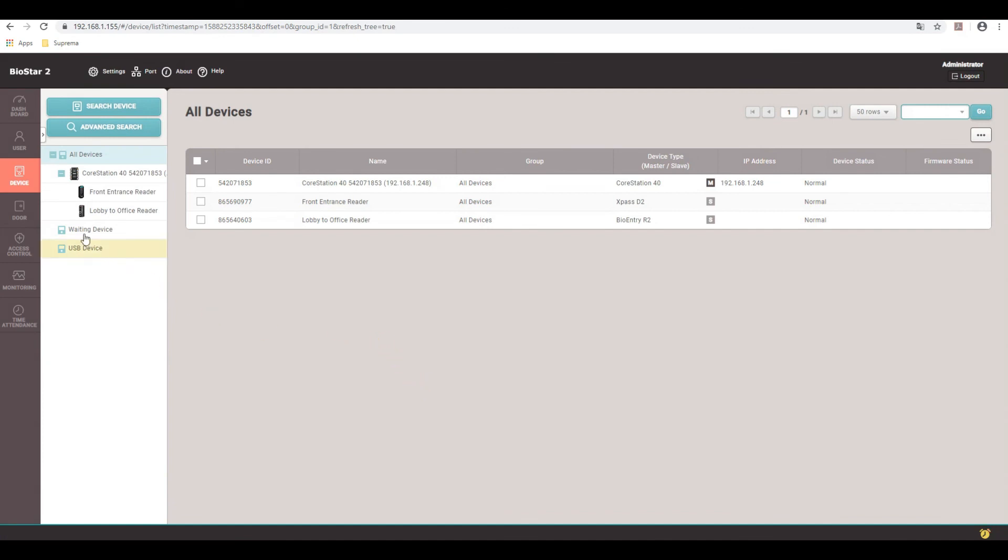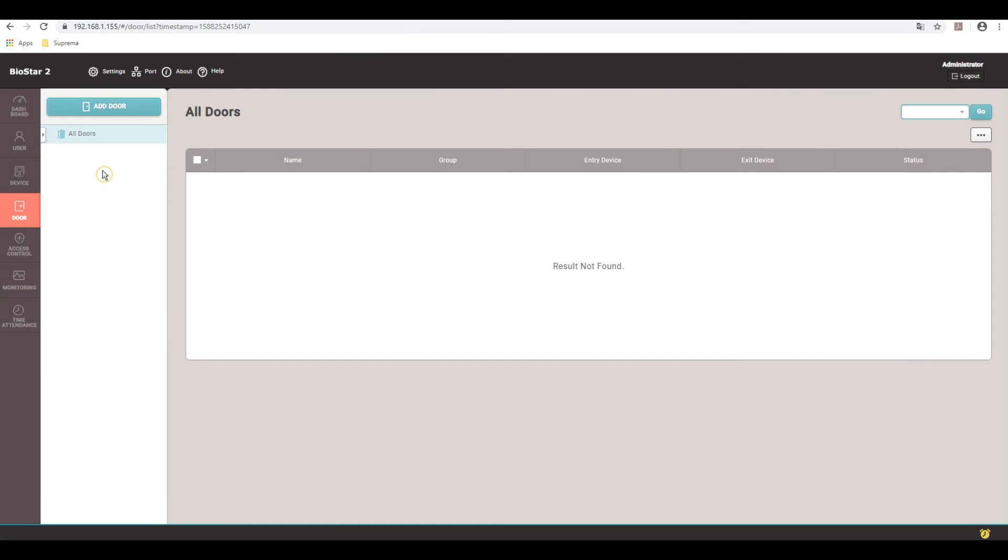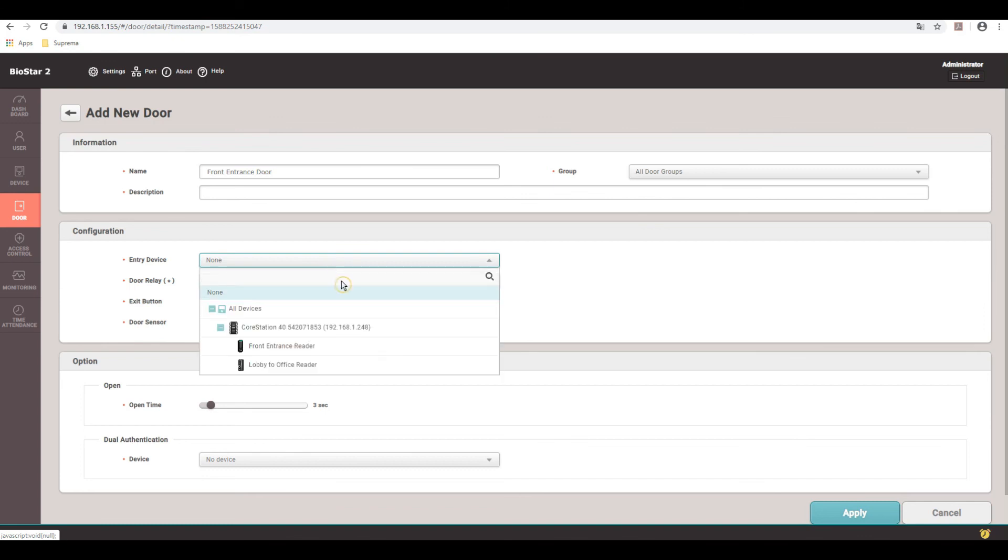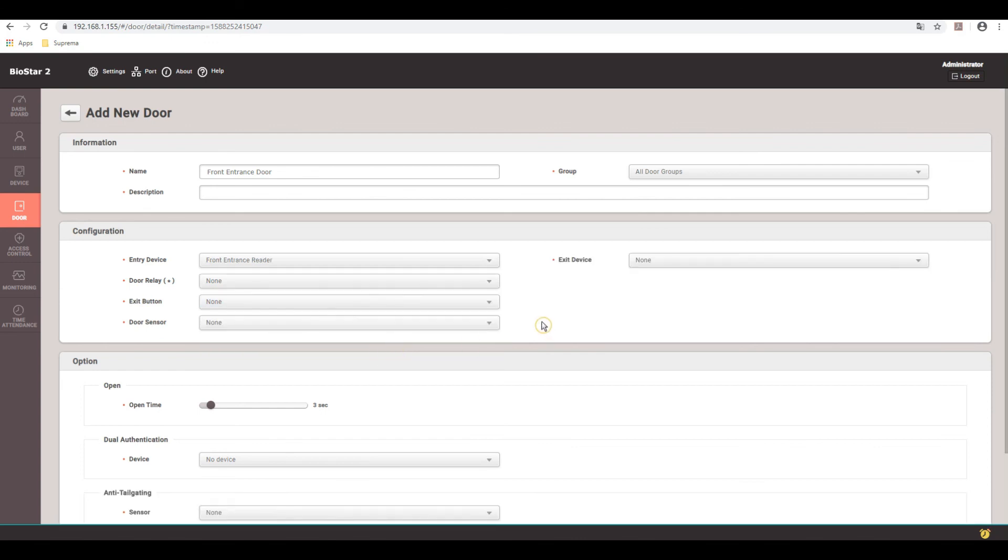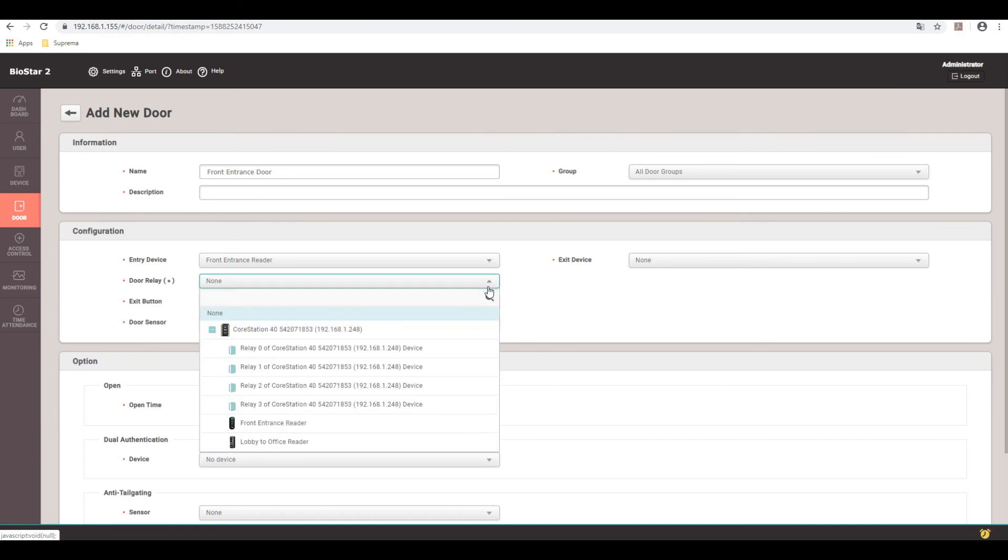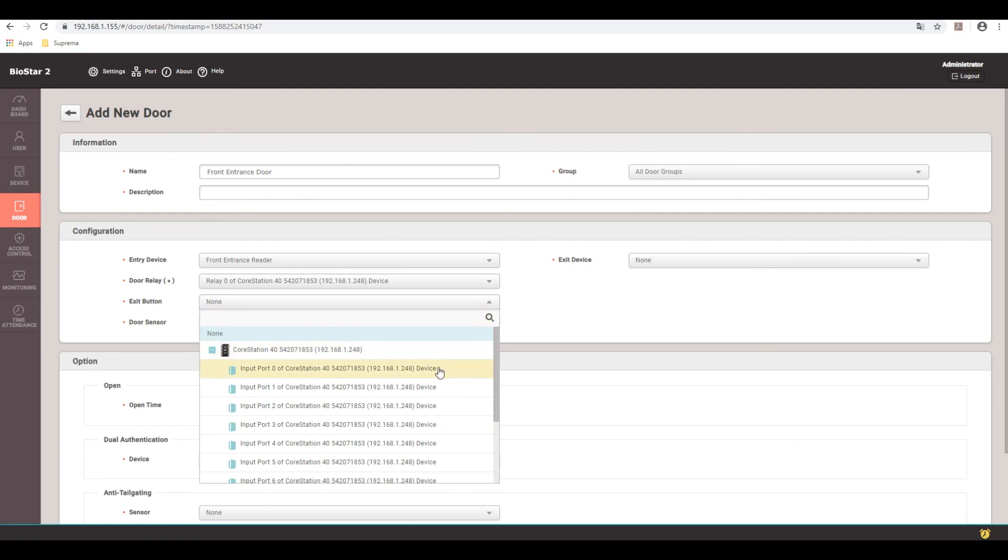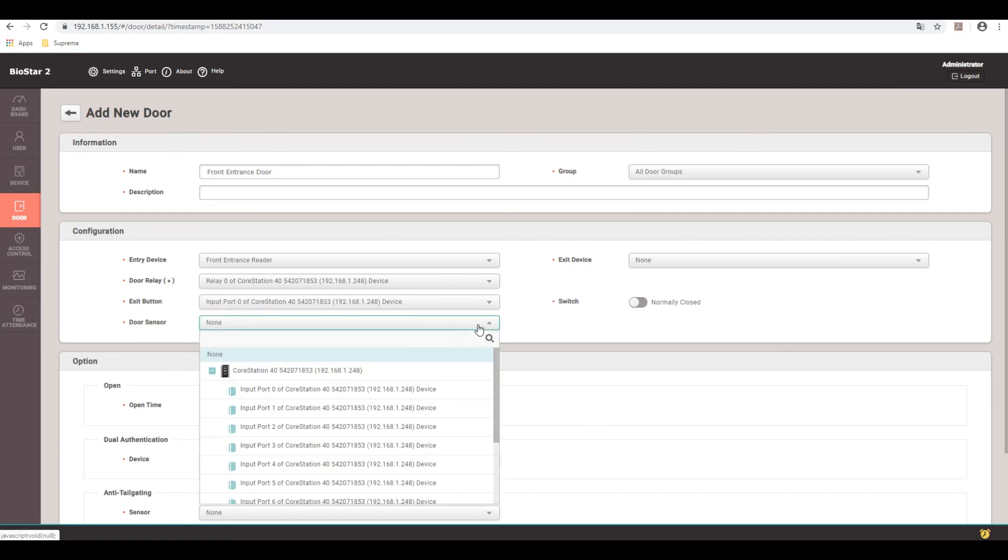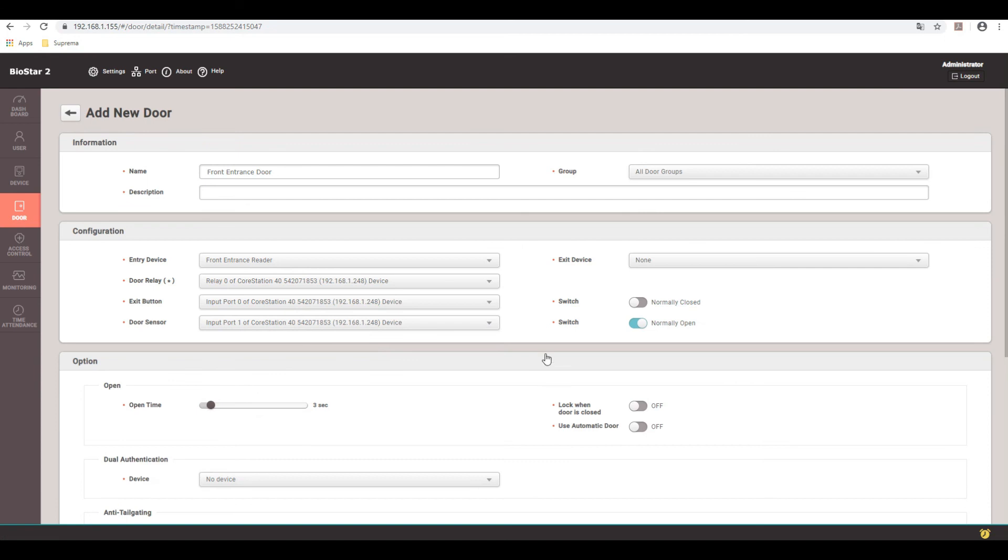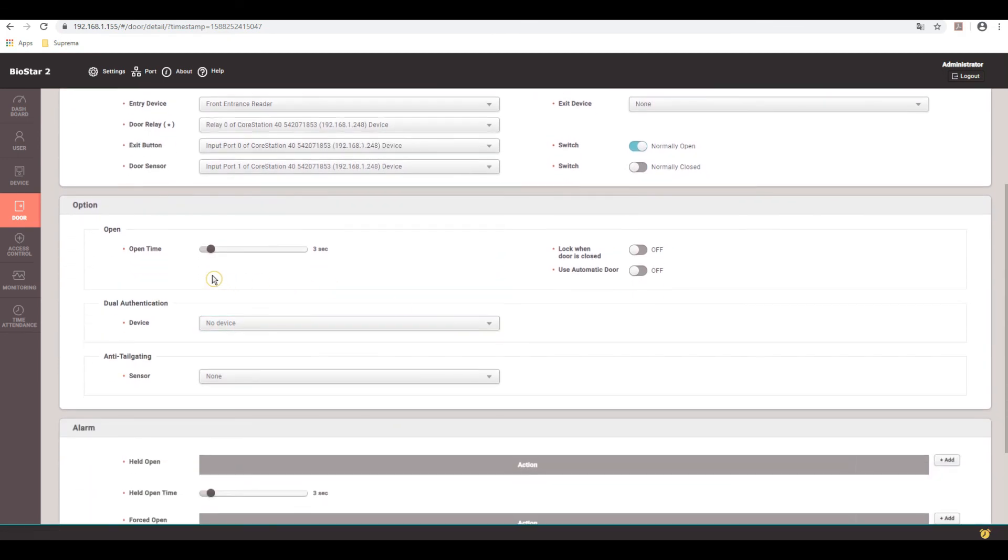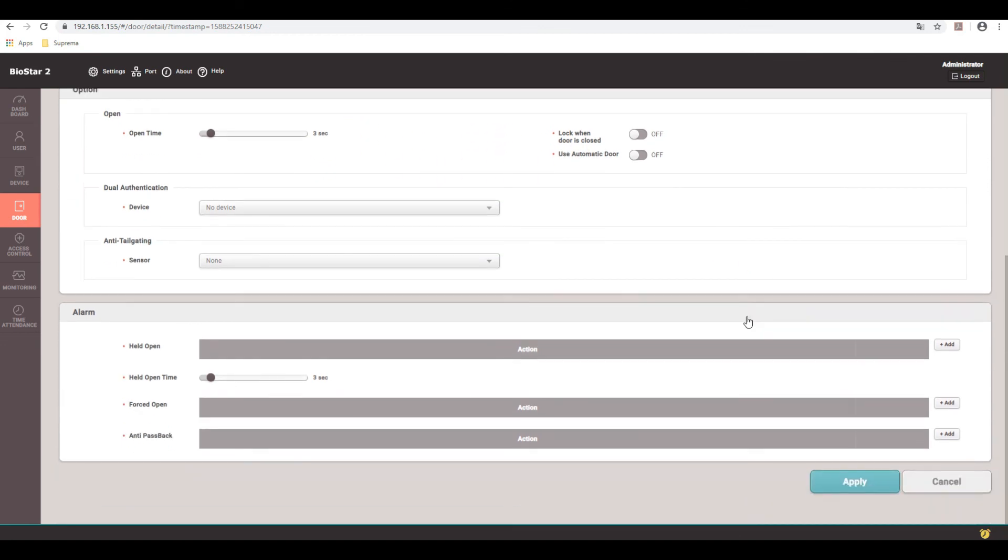Once you're done with that, we'll go ahead down to doors, click add door. We'll call this front entrance door. Now under this dropdown, you pick the device. Don't pick the core station. You'll actually pick the reader. I've seen people pick the core station and it's not working because it's not an actual reader. So do front entrance reader. Now that's wired into door port zero of the core station. So we're going to select relay zero. And then for the exit button, it is wired into input zero as well. And then the door sensor is input one. So my exit button is actually normally open. And then my door position switch door sensor is normally closed. So just scroll down. This is the time of seconds the relay will be engaged with a valid entry or card present or when the rex is triggered. So hit apply.